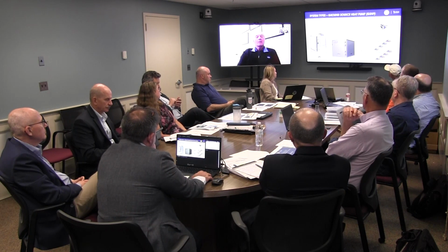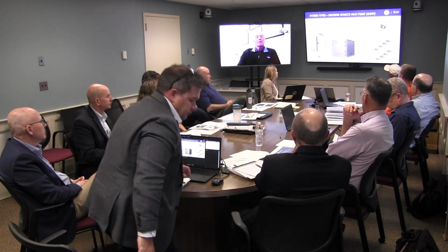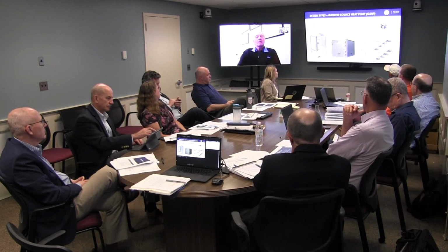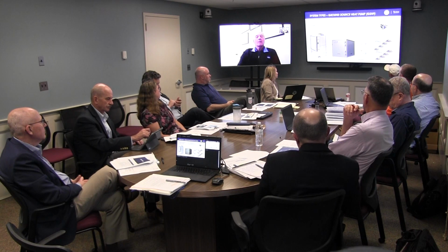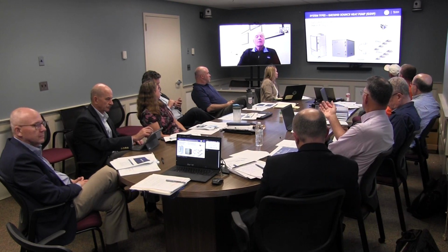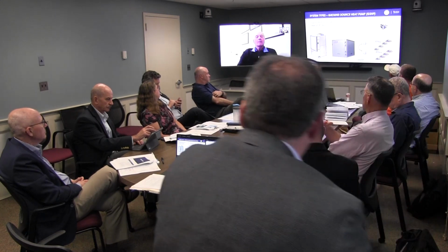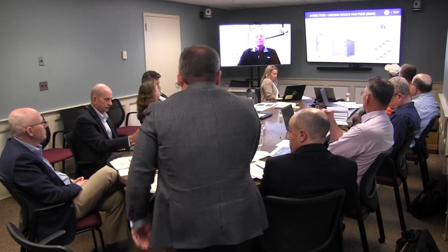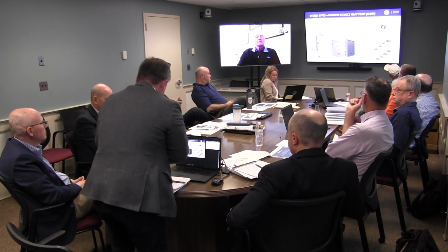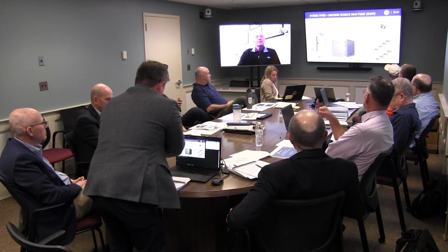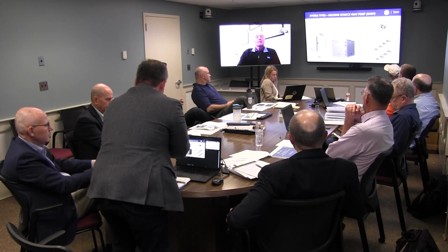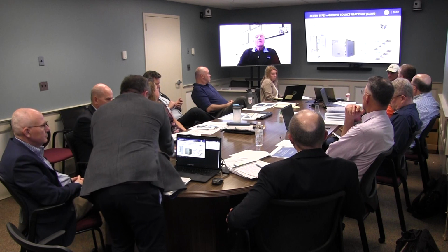So ground source heat pumps, this is a couple of different looks at what they are. The unit on the left is a water-to-air heat pump, which basically sends out hot or cold air to heat or cool your spaces. The unit in the middle is a water-to-water heat pump that uses your geothermal to create chilled water or hot water to be used for cooling through multiple types of chilled beams, fan coils, air handlers, etc. And on the right is a water-cooled VRF system, which we're really not going to explore. Geothermal also gives us an option to use water-cooled equipment in your kitchen. So your freezer and cooler can be water-cooled as well.